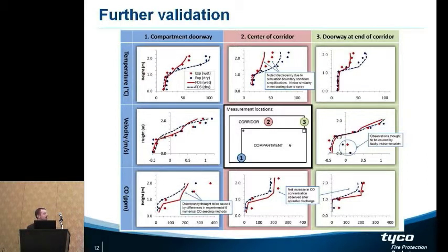We stuck the sprinkler in, and what we find with this calibrated spray is very reasonable reductions. The change in temperature is very close, it's the right delta T, even though some of our boundary conditions for the simulations weren't perfect because of the complexity of the experiments. We still see the right change in temperature, the right trends in the change in velocities, and the right trends in the change in the species we're measuring in the flow. There isn't necessarily a rigorous uncertainty analysis done here, and I know that. But this is just to show you an example now that we've gone through this process.